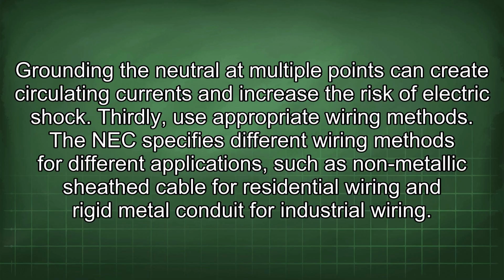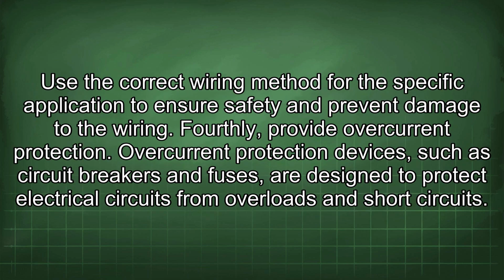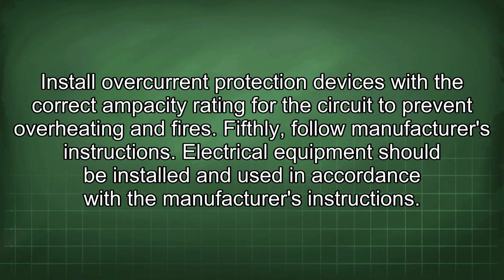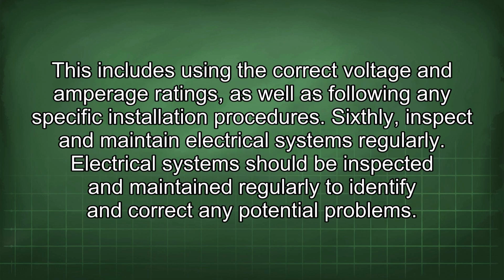Thirdly, use appropriate wiring methods. The NEC specifies different wiring methods for different applications, such as non-metallic sheath cable for residential wiring and rigid metal conduit for industrial wiring. Use the correct wiring method for the specific application to ensure safety and prevent damage to the wiring. Fourthly, provide overcurrent protection. Overcurrent protection devices, such as circuit breakers and fuses, are designed to protect electrical circuits from overloads and short circuits. Install overcurrent protection devices with the correct ampacity rating for the circuit to prevent overheating and fires. Fifthly, follow manufacturer's instructions. Electrical equipment should be installed and used in accordance with the manufacturer's instructions. This includes using the correct voltage and amperage ratings, as well as following any specific installation procedures.